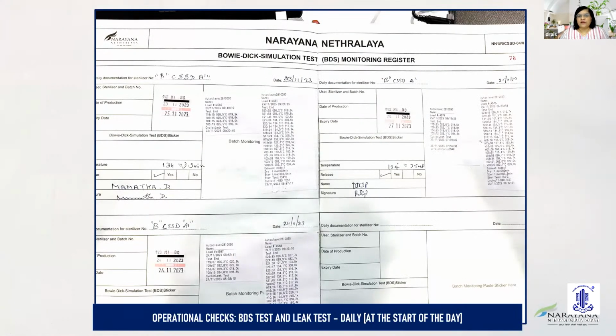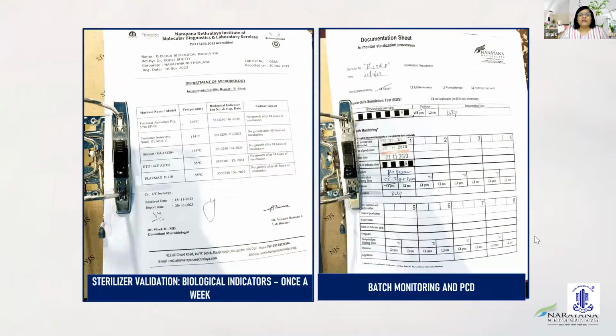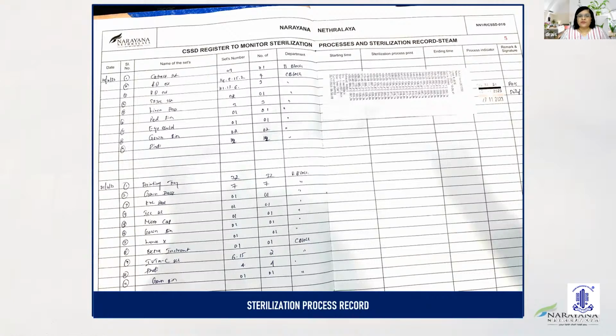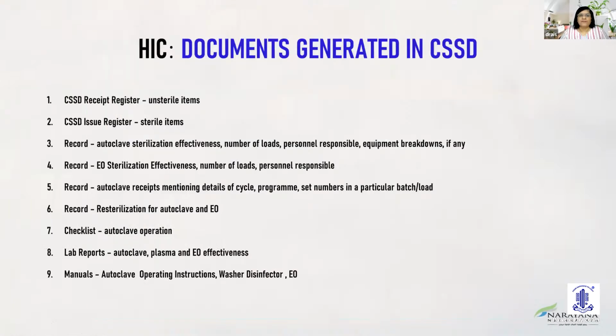Now, this is the BD monitoring register. As you can see, these are operational checks. BD test and leak test are done daily at the start of the day. This is the sterilizer validation with biological indicators, which we do once a week, and batch monitoring and PCD, which is done. This is the sterilization process records, which are duly maintained.